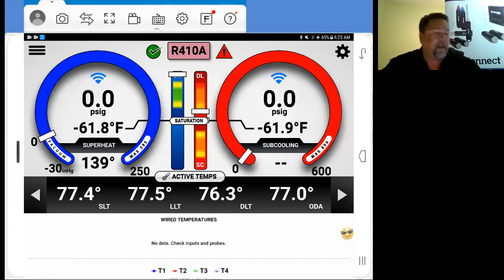Okay, so now we've got all of our temperatures showing. Now we're going to be placing our supply and return probes. Where do we put these things? A long time ago, when we first started this, everybody was placing these probes just above the evaporator. They put their supply line just 4 inches above the evaporator. Not exactly the best choice. The supply side, use the first available, the best register that you can. Don't go right above the coil.